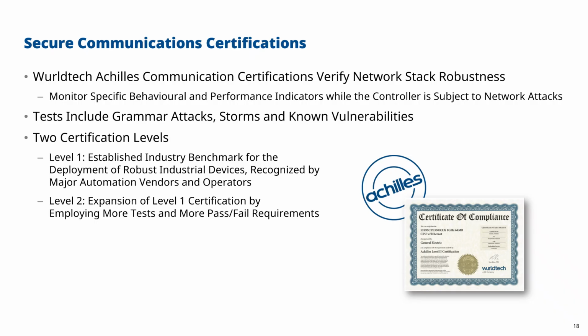Pending full IEC 62443 certification, Emerson already has certifications for secure communications. We work with the Wurldtech Achilles communication certifications, and with these tests we verified our network stack robustness, monitoring specific behavioral and performance indicators while the controller is subject to network attacks to make sure it functions correctly. This includes grammar attacks, network storms, and known vulnerabilities for particular types of stacks.